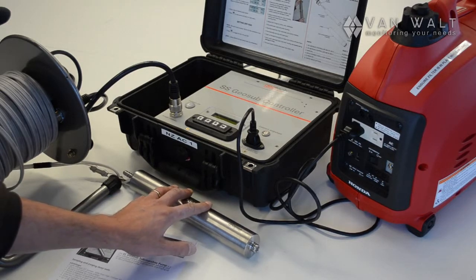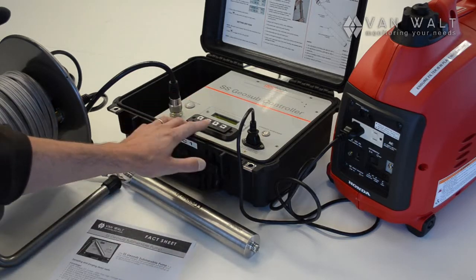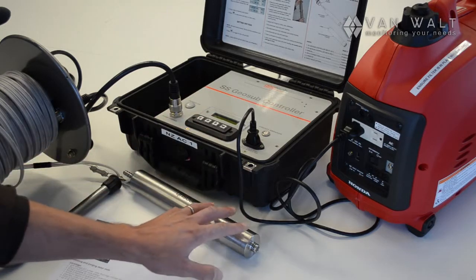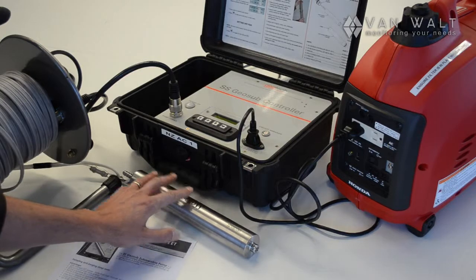The maximum flow rate on this at one meter is up to 16 liters a minute but we have a fully variable speed control so you can indeed low flow sample with this pump or you can high flow with it.